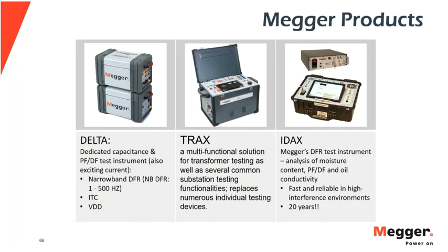We just passed the over 20-year mark from when we introduced the first commercially available DFR test instrument. We're really proud to have made this technology accessible to so many people. Suffice it to say that Megger has a lot of experience with this test, and of course you'll find the ITC capabilities with this instrument as well, and the ability to convert DFR results to a thermal response. Again, that's power factor versus temperature.